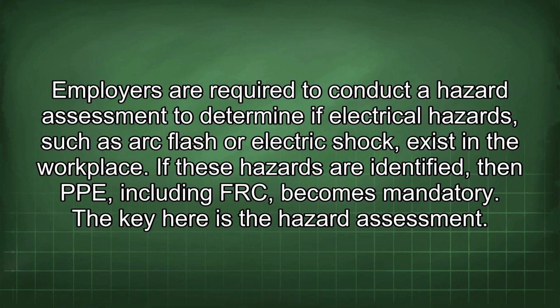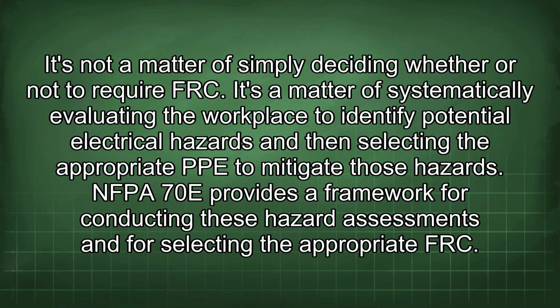If these hazards are identified, then PPE, including FRC, becomes mandatory. The key here is the hazard assessment. It's not a matter of simply deciding whether or not to require FRC. It's a matter of systematically evaluating the workplace to identify potential electrical hazards and then selecting the appropriate PPE to mitigate those hazards. NFPA 70E provides a framework for conducting these hazard assessments and for selecting the appropriate FRC.